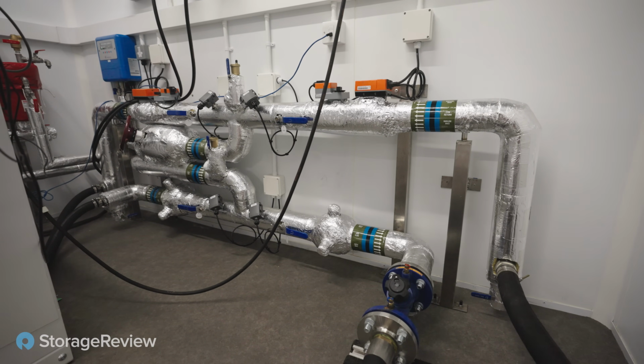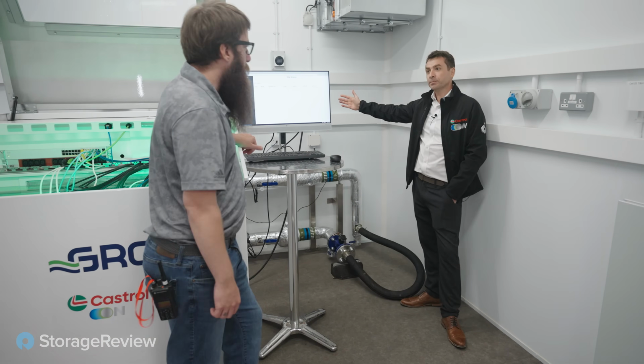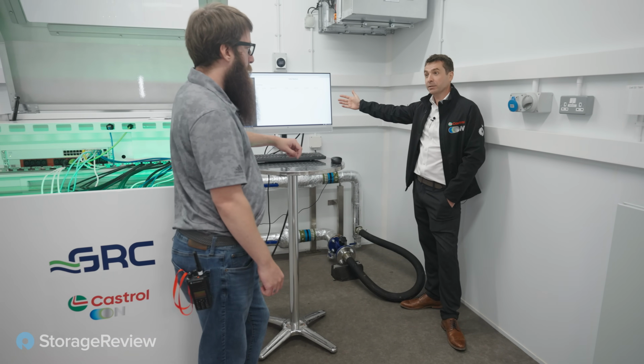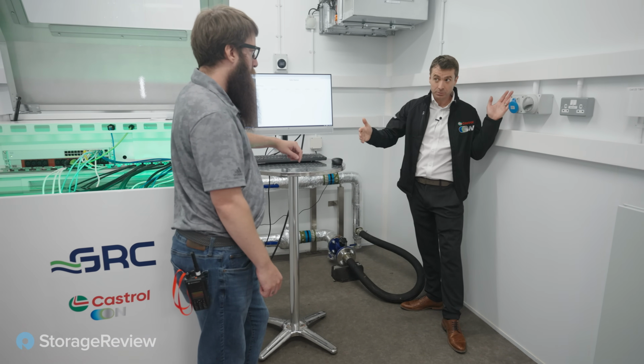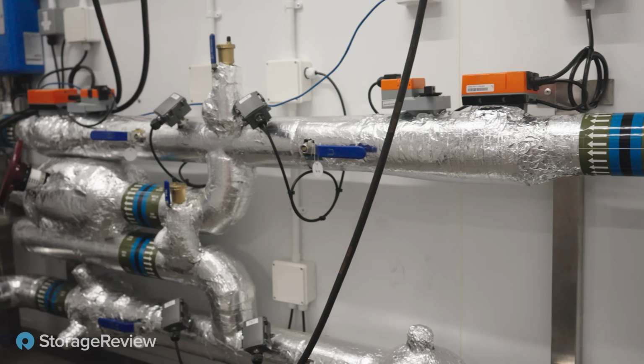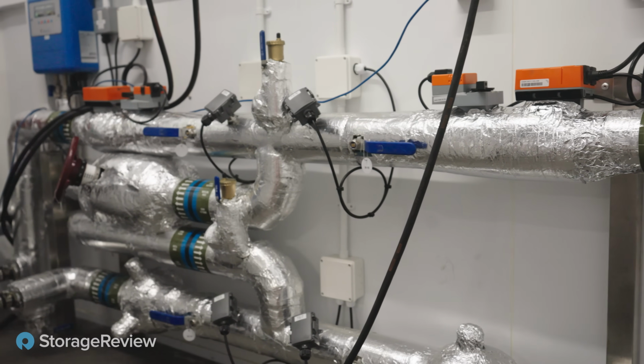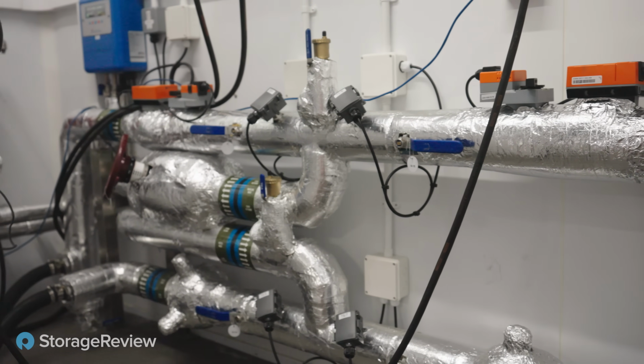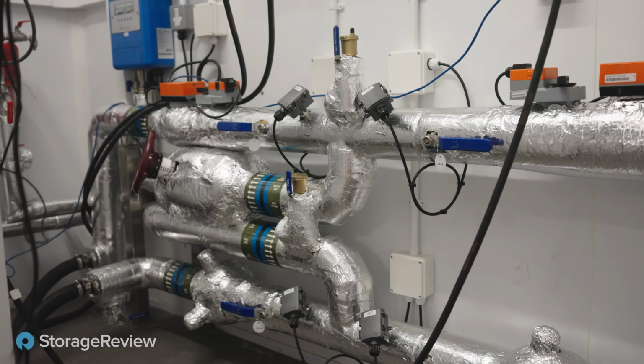And around the back here, you can see our heat rejection circuit. So our secondary circuit, our water glycol circuit, is fed out to a dry cooler. Our dry cooler has 100 kilowatts of capacity, so that feeds 2 of these test cells. And there's no refrigeration cooling in here either - because of the high heat of the dielectric fluid, we can handle dry cooling, free cooling year round.